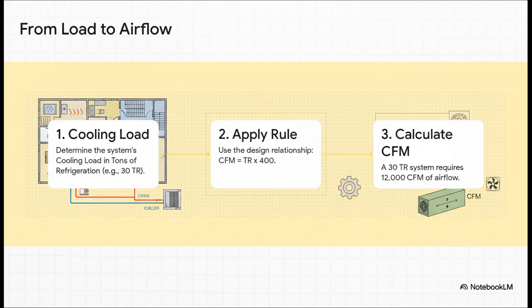So the very first number we need to nail down is the airflow. It starts with figuring out the building's cooling load, measured in tons of refrigeration, or TR. A common rule of thumb in the industry for standard comfort cooling is a simple relationship: take the TR value and multiply it by 400. So let's say we're working with a 30-ton system. We just do the math: 30 times 400 gives us our magic number, 12,000 cubic feet per minute, or CFM.